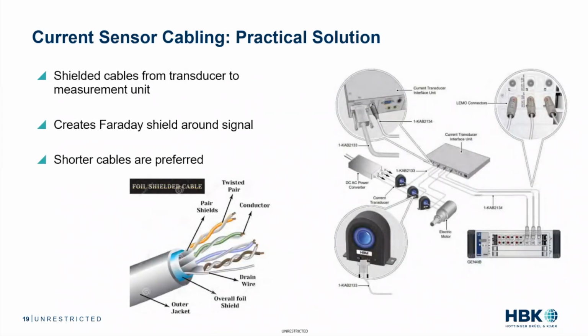And then connecting from the CT to, let's say, the power supply of the CT, you want to have shielded cable as well. And here we're showing not only shielded cable, but it's also a twisted pair. This is going to create a Faraday shield around the signal, and shorter cables are preferred. And the shielded cables are from the transducer to the measurement unit.